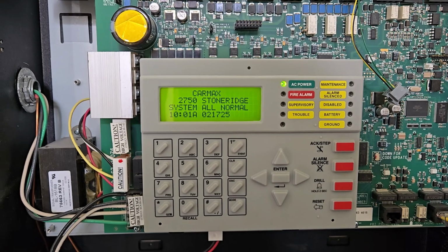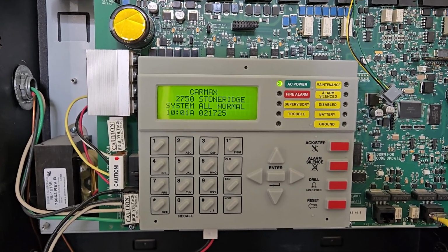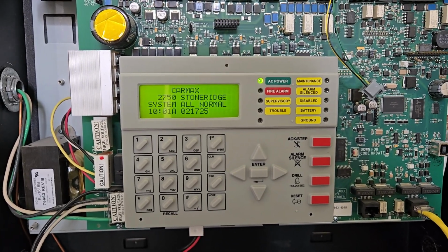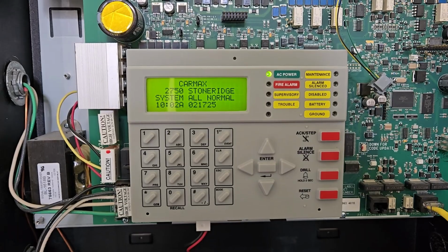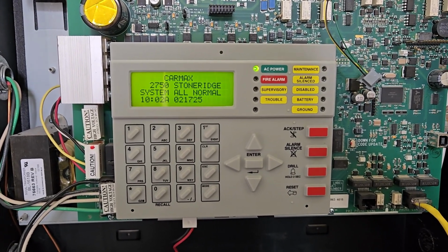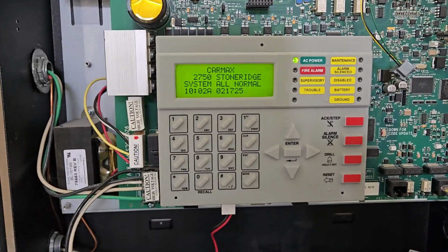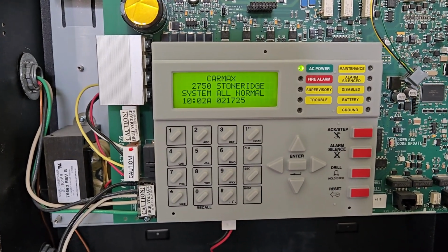So we're at 1 minute right now. And like I said, we're just going to wait to make sure we get that signal. And once we get it, we could plug the phone line back in and clear it. And then you can check with your monitoring, whether you have an application for monitoring signals, or you can call into monitoring to verify if it reported to the monitoring agency. So here, though, we're just going to test that it comes into the fire panel.